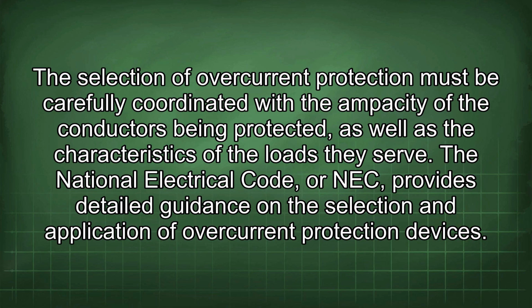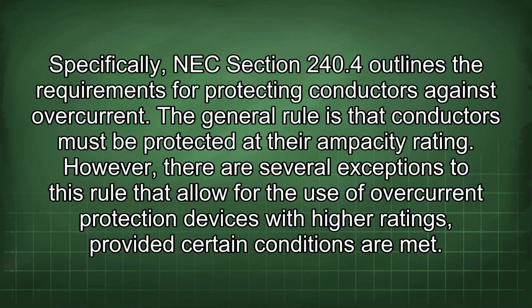The National Electrical Code, or NEC, provides detailed guidance on the selection and application of overcurrent protection devices. Specifically, NEC Section 240.4 outlines the requirements for protecting conductors against overcurrent. The general rule is that conductors must be protected at their ampacity rating. However, there are several exceptions to this rule that allow for the use of overcurrent protection devices with higher ratings, provided certain conditions are met.